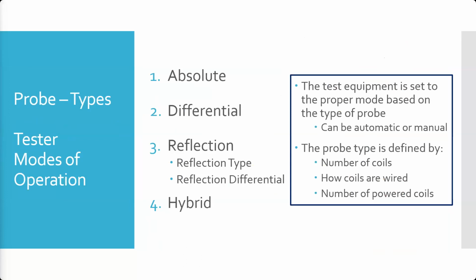You get some really weird results, or it's really, really hard to get it to work, if you have it set for the wrong probe type. So you have to pay attention. What is the probe type? Now with a hybrid probe, which a lot of our probes are, they're going to primarily act more like an absolute. It might be a combination, but you may have to set it. You'll use the reflection setting, or you'll use the differential setting. You might set it on the reflection setting, but it may have a certain amount of behavior like a differential probe.